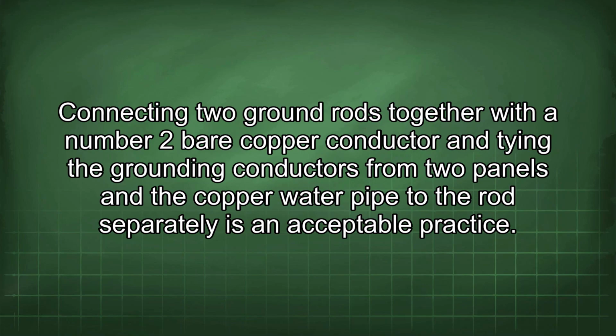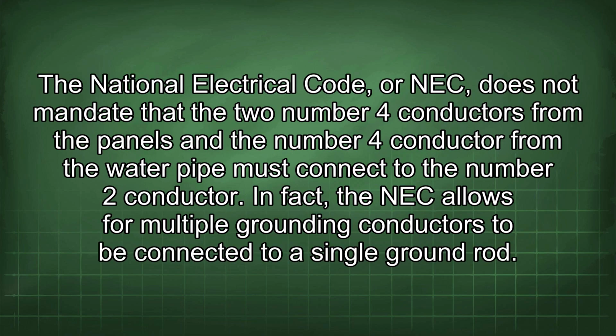Connecting two ground rods together with a number 2 bare copper conductor and tying the grounding conductors from 2 panels and a copper water pipe to the rod separately is an acceptable practice. The National Electrical Code, or NEC, does not mandate that the 2 number 4 conductors from the panels and the number 4 conductor from the water pipe must connect to the number 2 conductor. In fact, the NEC allows for multiple grounding conductors to be connected to a single ground rod.